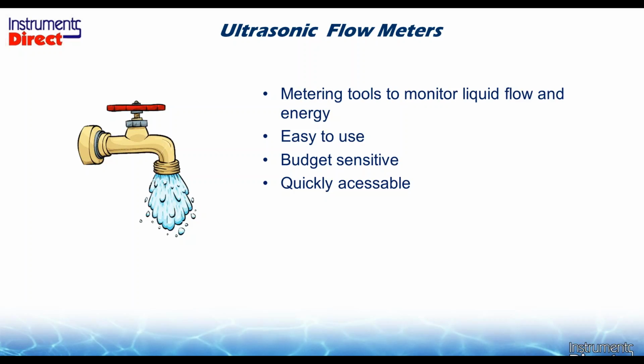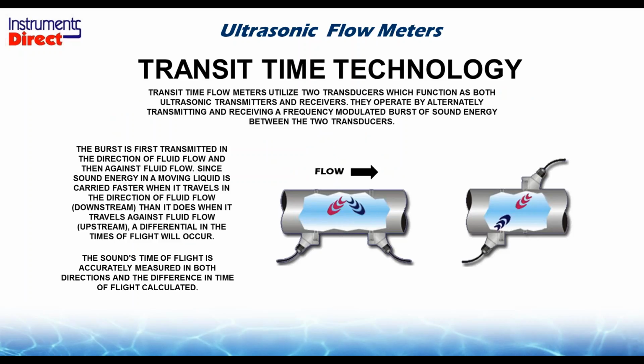Now you don't have to make a capital investment. You can rent something by the week, so anybody can get access, and it's easy to use and readily available. The technology that I'm talking about is a clamp-on technology. In order to do energy, we need to do flow and we need to do temperature. In this case, we start off with flow. This is called an ultrasonic transit time flow meter.